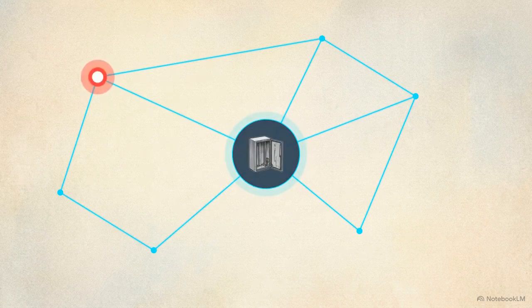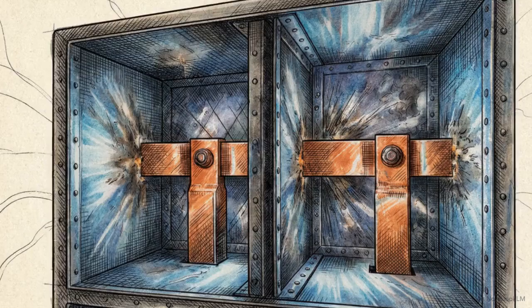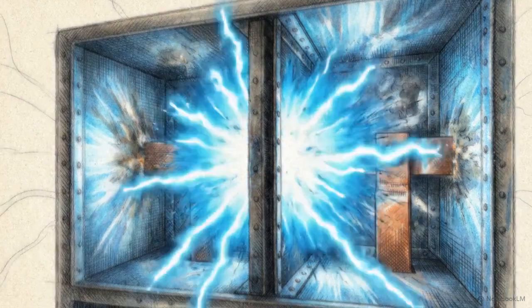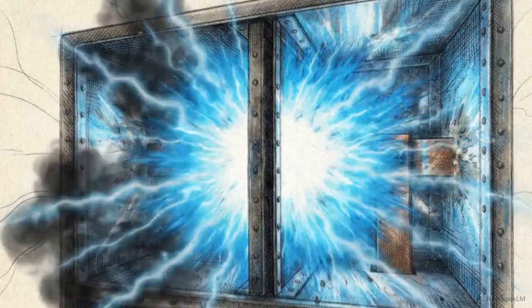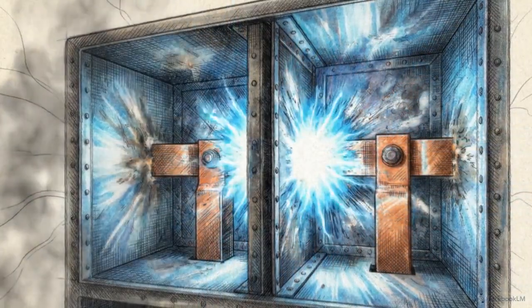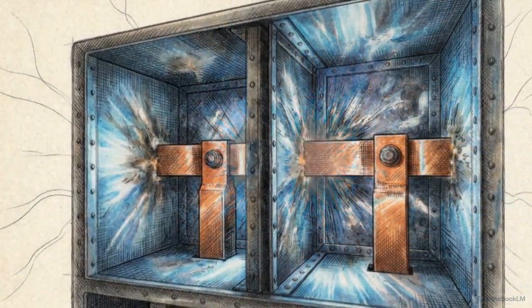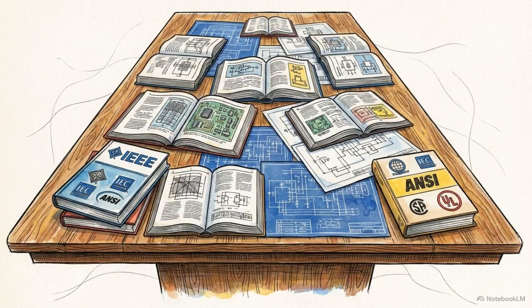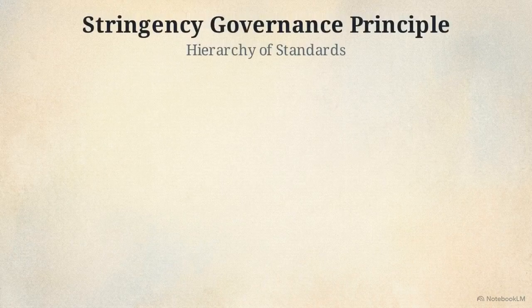A DC distribution board, or DCDB, functions as an internal firewall for electrical grid facilities. It contains high-energy faults to a single panel, preventing localized surges from triggering cascading failures across the wider substation network. Validating this hardware requires field engineers to reconcile competing manufacturing and safety thresholds from organizations like the IEC, IEEE, and NEMA.